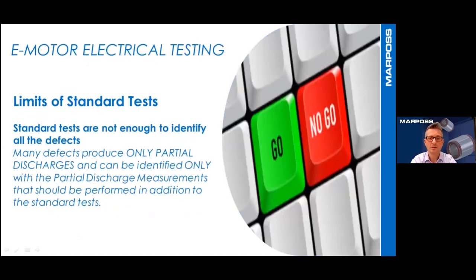The standard electrical tests described are not enough to identify all types of failure. That's to say that they are useful if wire insulation is already damaged. But if wires have only a contact with another one or with the housing without damage, the limits of the test become obvious, because the testing voltage should be high enough to cause high energy discharge that completely opens the insulation materials between the two contact points. Many defects produce only partial discharge and can be identified only using the partial discharge method, which does not replace the standard test, but has to be performed in addition to the standard test.